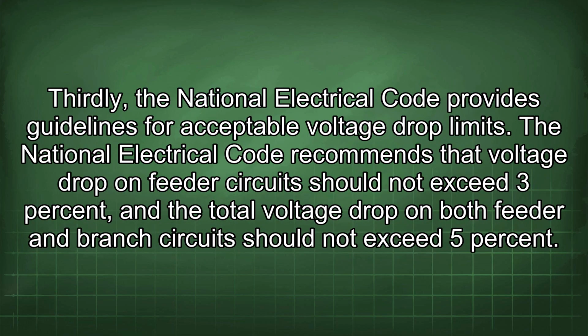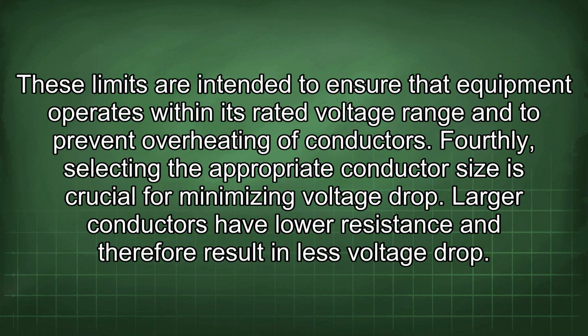Thirdly, the National Electrical Code provides guidelines for acceptable voltage drop limits. The National Electrical Code recommends that voltage drop on feeder circuits should not exceed 3%, and the total voltage drop on both feeder and branch circuits should not exceed 5%. These limits are intended to ensure that equipment operates within its rated voltage range and to prevent overheating of conductors.